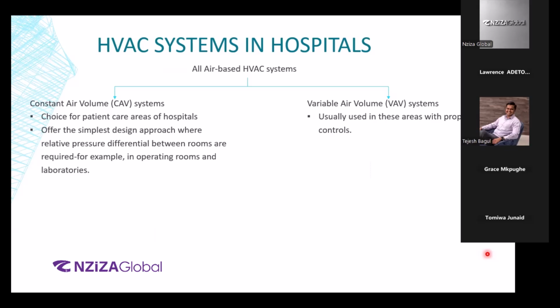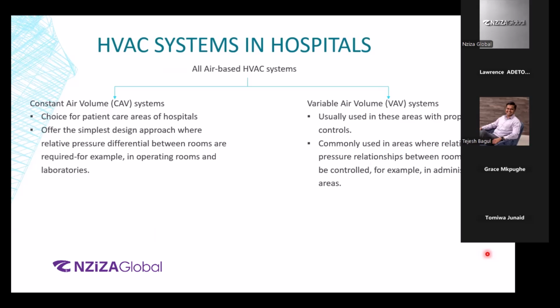So now think about this. Let's say you have 10 operating rooms in a hospital. Out of that, only 3 are being utilized, right? So with the variable air volume system, we'll talk about the system in specific, you can just keep the variable air volume devices for those 3 operating theaters on. The rest 7 can be off, right? But if you're doing that, you need to vary the airflow that is going through just those 3 VAV devices, right? So for that reason, it is very popular when it comes to proper pressurization with the help of proper controls as well.